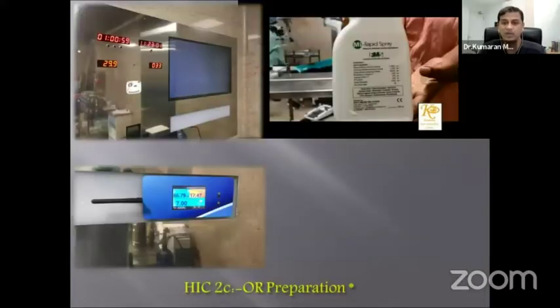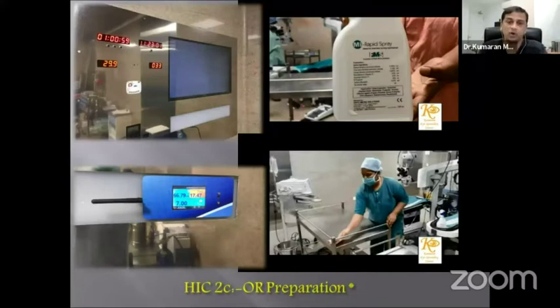If you have an HVAC system or a non-HVAC system, it's always good practice to switch on the air conditioner in an HVAC system at least 1 hour before starting your theater, so the pressure, humidity, and temperature settings are attained. In a non-HVAC system, it's also good practice to switch on at least an hour before, so that all the toxic fumes used to fumigate the theater are gone.